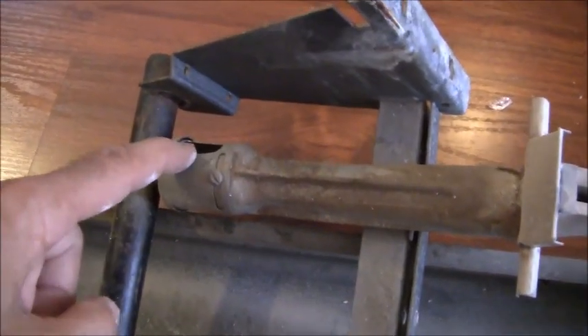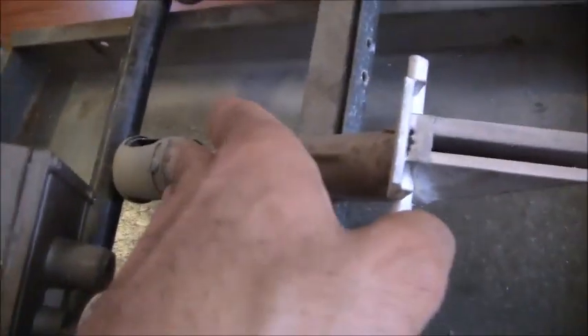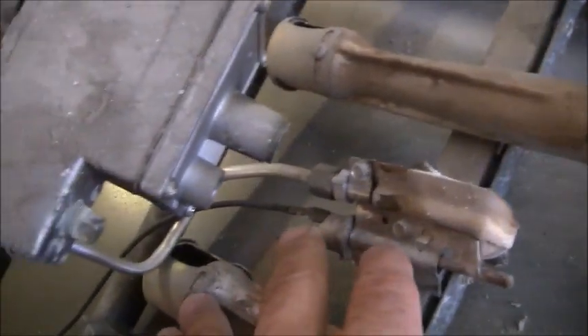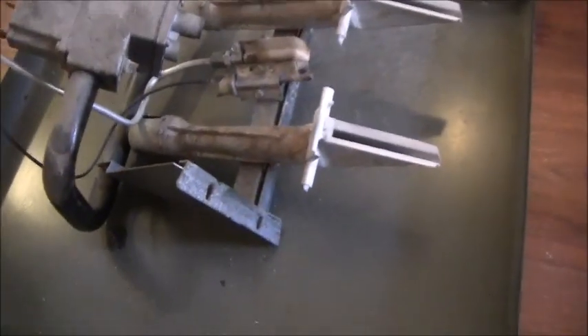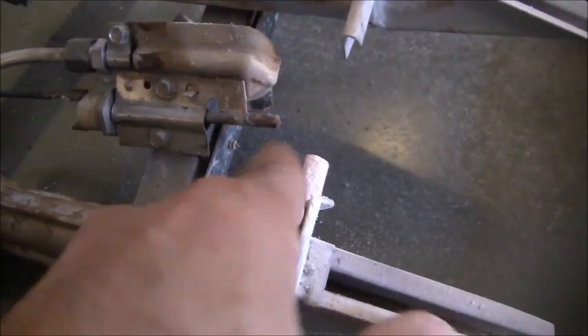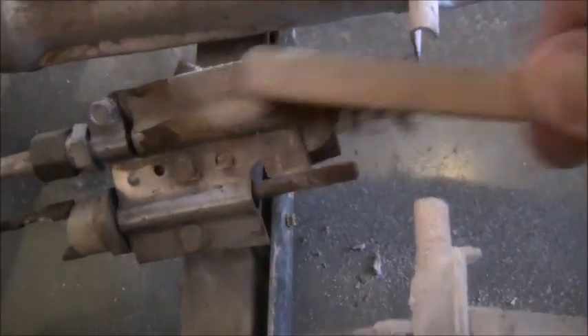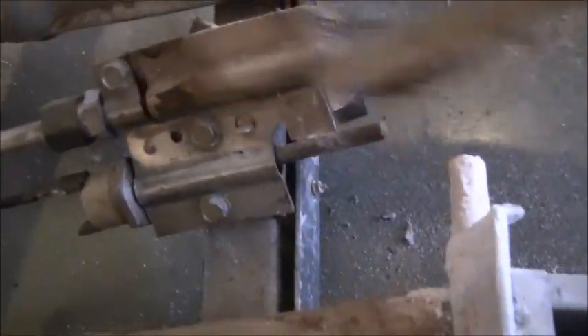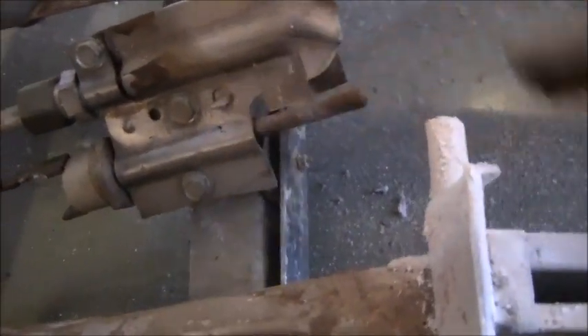While I'm looking at the burners, I'm looking for anything dirty, anything that's out of the ordinary there, but I'm not going to adjust these primary volume dampers here for the primary air, because I'm going to just make an assumption that everything is preset either at the factory or whatever. We'll check our burner operation when we get into it. Now, as far as this thermocouple goes, I think I'm going to get a little wire brush and just clean that off a little bit. Alright, so I have a little wire brush here, and even though this thermocouple works, I'm just going to clean off everything here, just doing preventive maintenance to make sure everything is clean, give it the best chance of running.